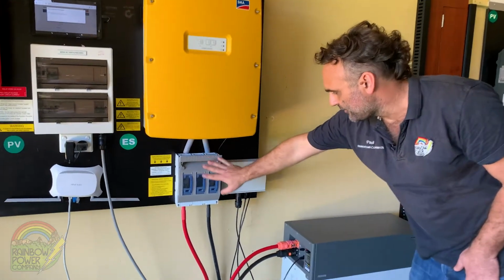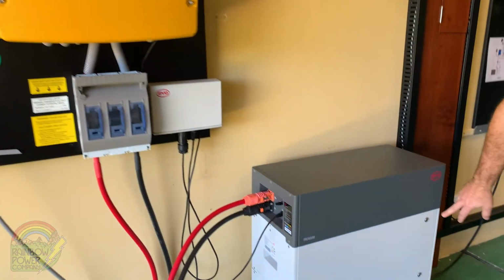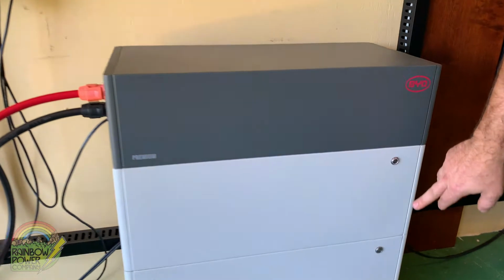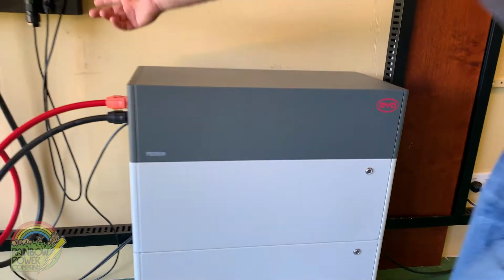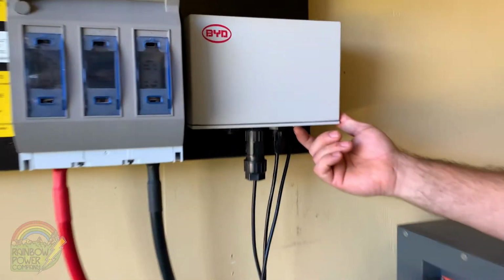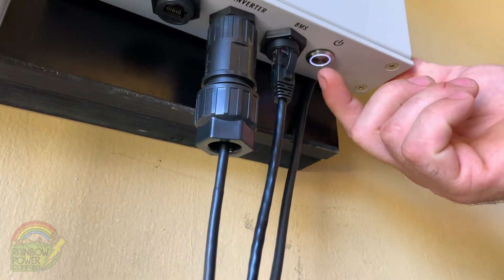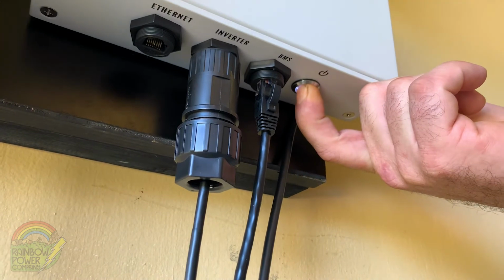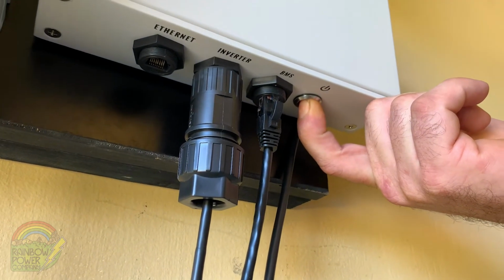If we come down through the main HRC fuse into the battery bank, we still have lights on the battery bank. To turn off the battery bank, we've got to turn off the switch on the BMU. It's a bit tricky - it's located on the bottom of the BMU. There's a little white switch here with a light. We hold that down and it takes nearly 5 seconds until the system turns off.